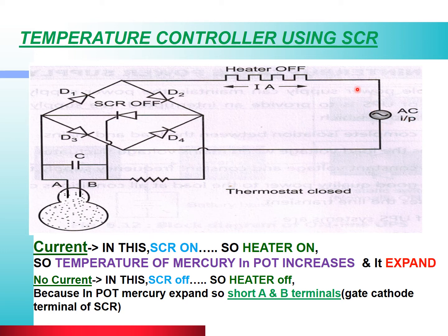First, we will see the input supply. The gate supply is given to the SCR, so the SCR turns on. After this, current flows as follows: from the positive input supply, through the heater, through diode D2, through the SCR, through diode D3, and back to the negative supply. This completes the current flow path and the heater turns on.